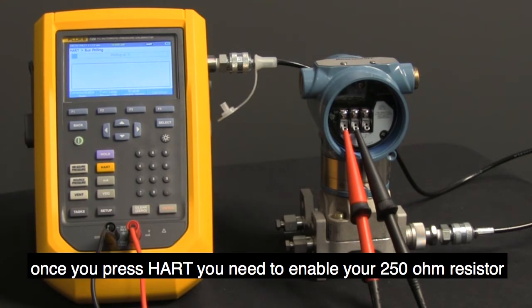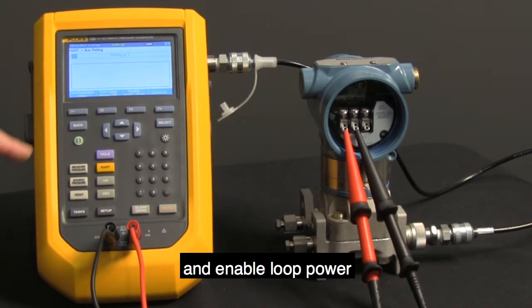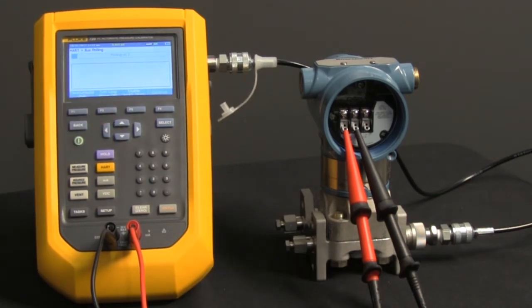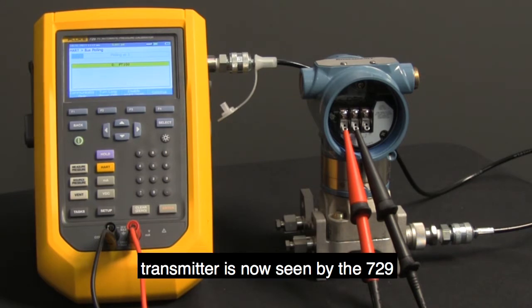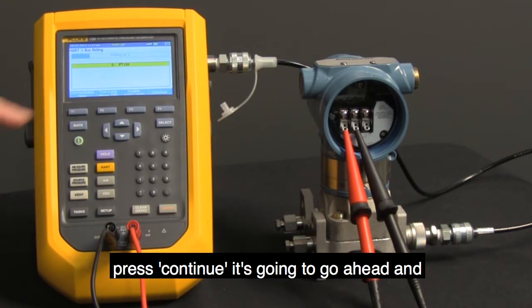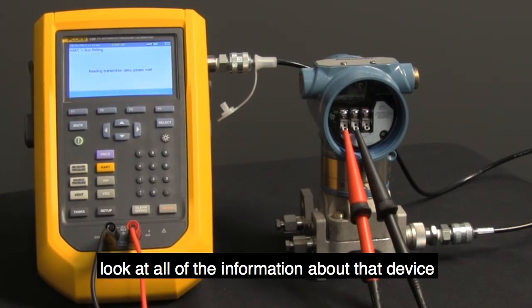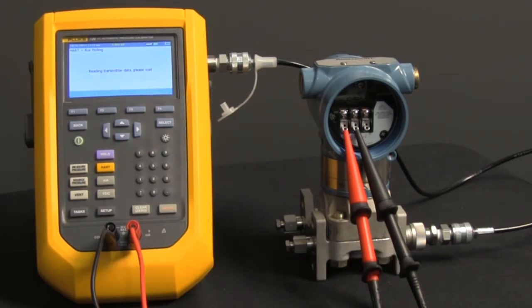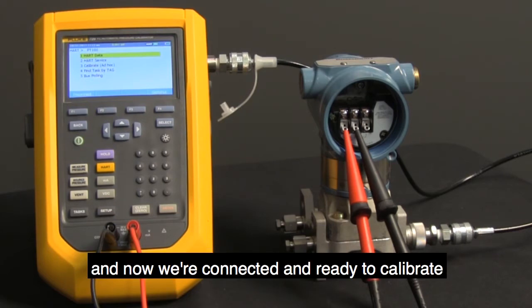Once you press HART, you need to enable your 250 ohm resistor and enable loop power. Transmitter is now seen by the 729. Press continue. It's going to go ahead and look at all the information about that device. And now we're connected and ready to calibrate.